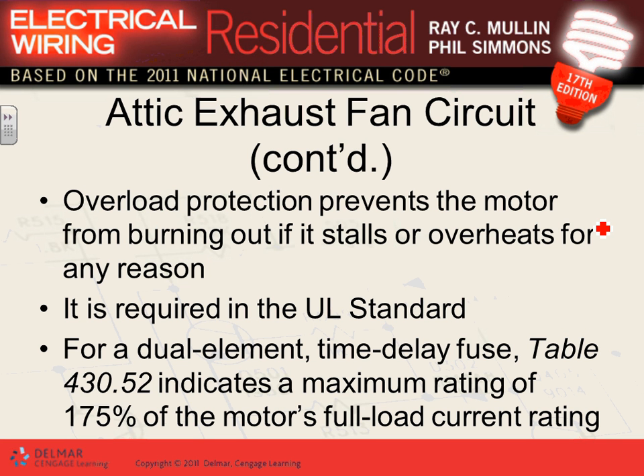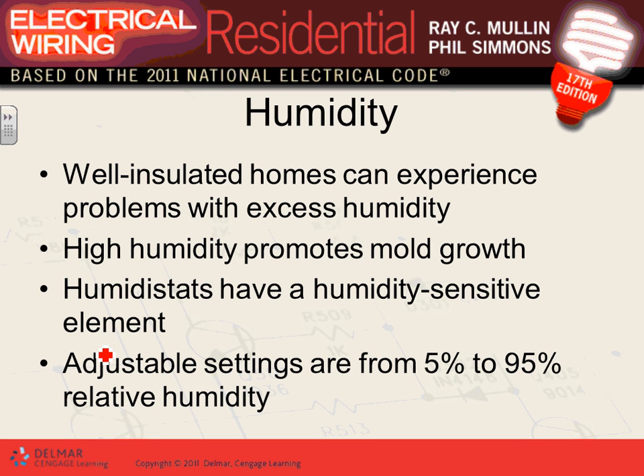Okay, so a lot of these fans have overload protection. Again, the same thing, to protect it. How to size the overcurrent protection device, if it's a fuse or a circuit breaker? Yesterday, I want to remind you guys, we were using this table. And we said if you're using a fuse, 175, using a circuit breaker, 250, is just the sizing requirement. So that's your attic.